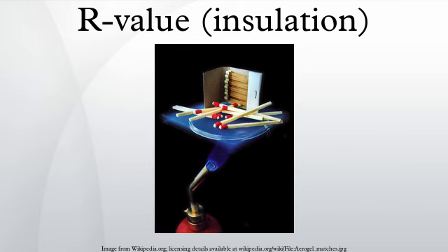For the most part, testing the R value of insulation is done at a steady temperature, usually about 70 degrees Fahrenheit, with no surrounding air movement. Since these are ideal conditions, the listed R value for insulation will almost certainly be higher than it would be in actual use. Because most situations with insulation are under different conditions, a definition of R value based on apparent thermal conductivity has been proposed in document C-168 published by the American Society for Testing and Materials. This describes heat being transferred by all three mechanisms: conduction, radiation, and convection.